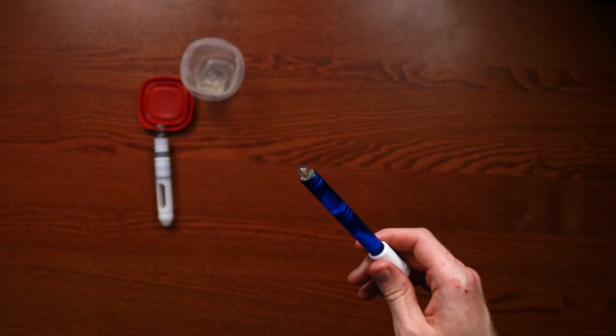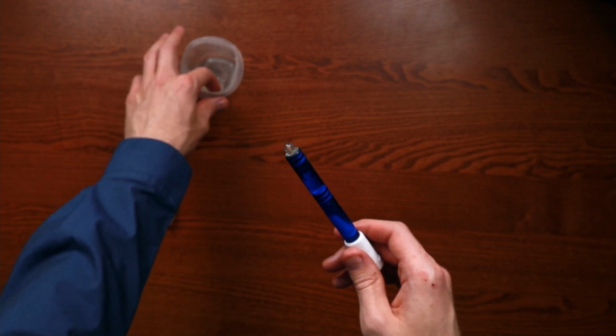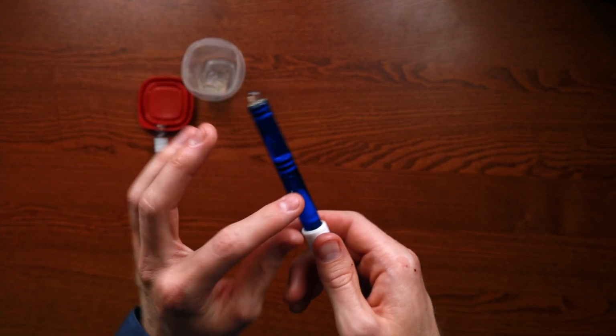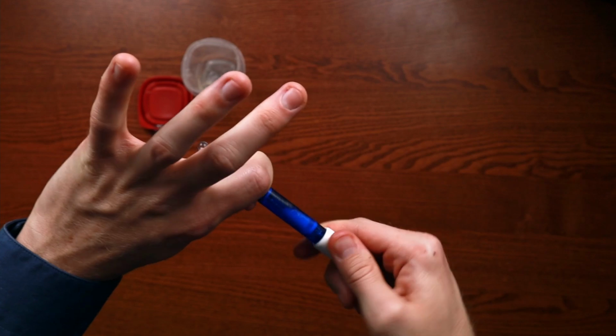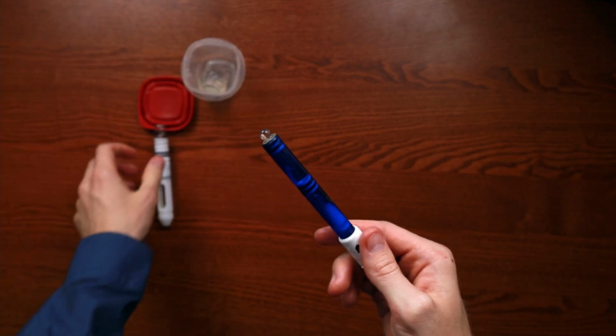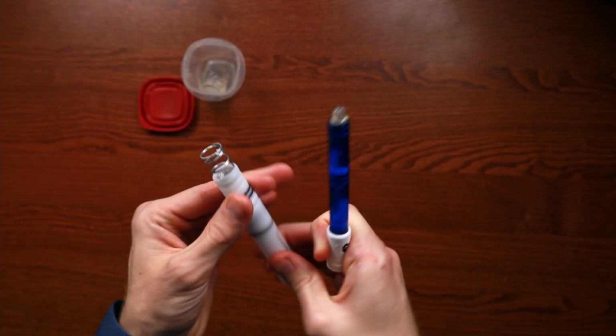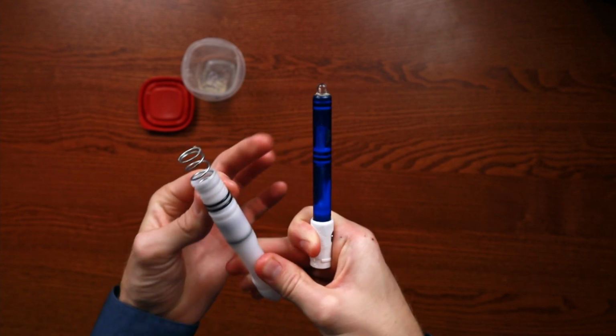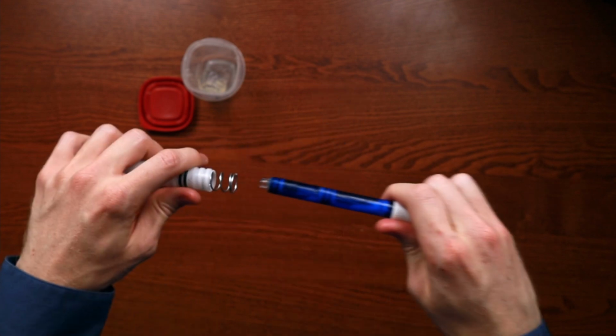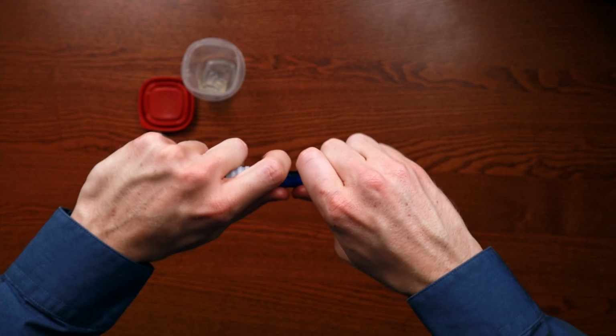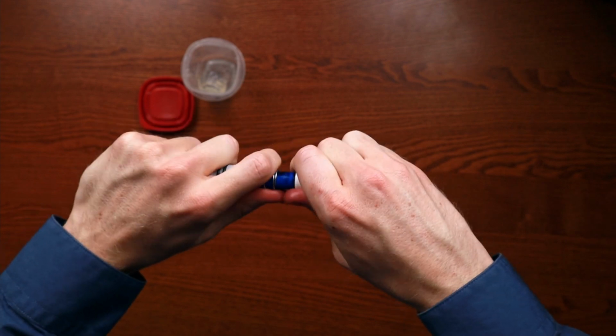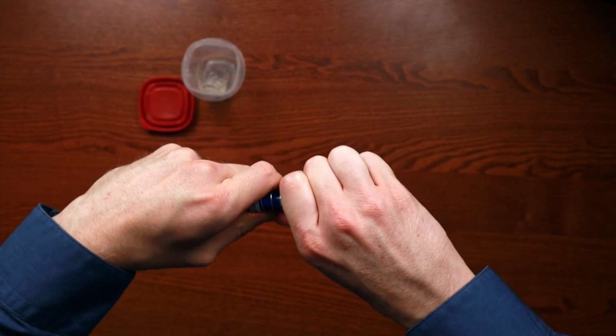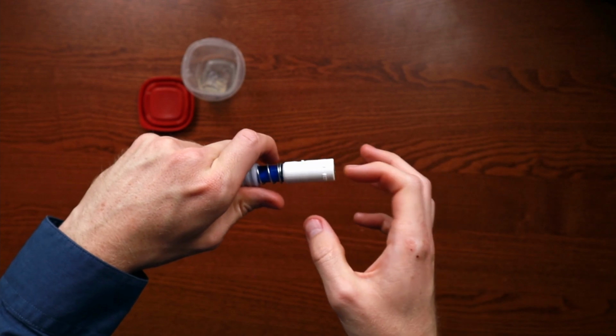We recommend lightly greasing the outside to ensure the long-term health of the inner O-rings, which are responsible for creating a watertight seal around the electrode. Now is also a good time to grease the outer O-rings on the electrode body. Once done, place the electrode back in the body and press down on the electrode cap until the cap contacts the spring. Retest the sensor and confirm that it is reading properly.